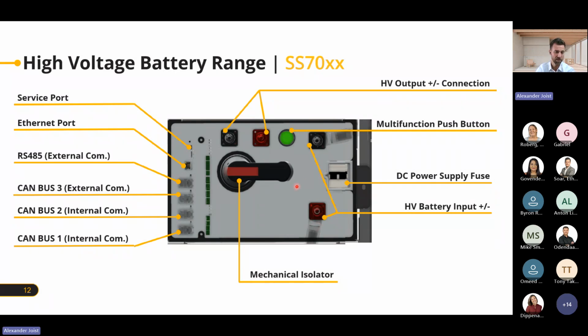And in the middle, the mechanical isolator, also very important. It's always on, it's the last thing you switch on, because that's the connection between the battery and the inverter or whatever is connected to it. So the mechanical isolator is always the last line of protection in a way, manual protection, where you can switch on or switch off the whole battery stack.